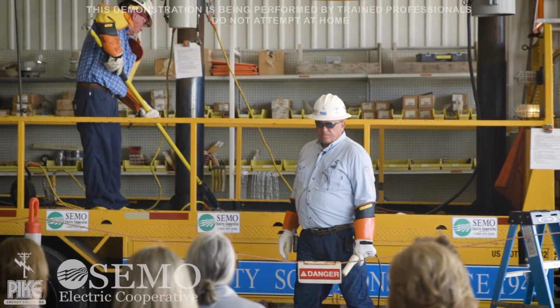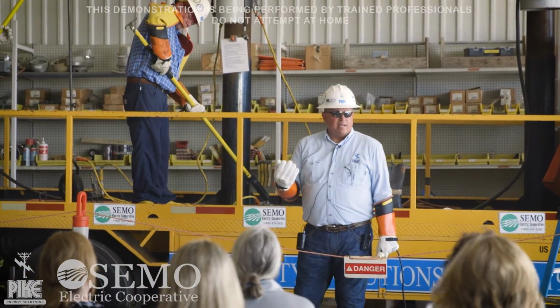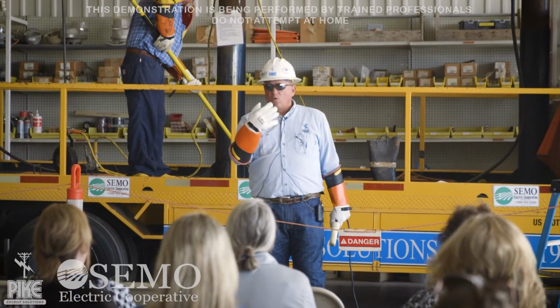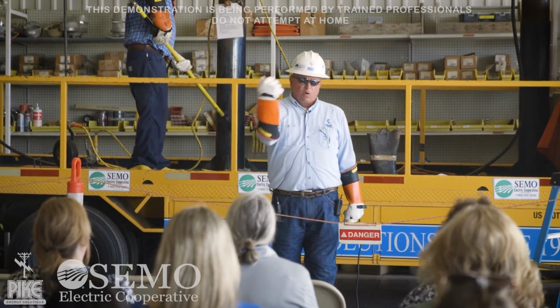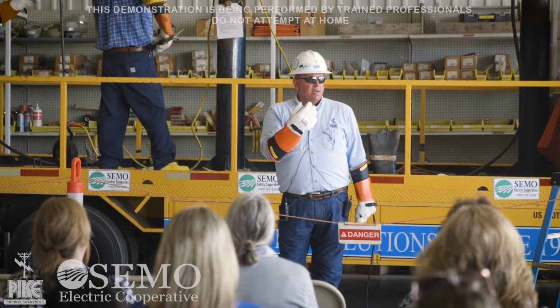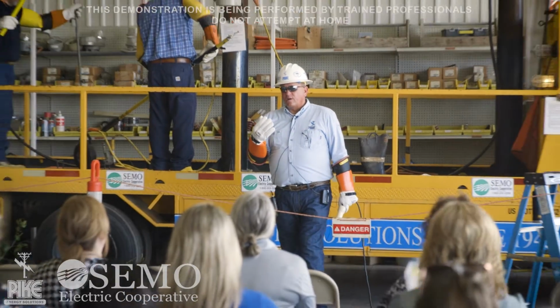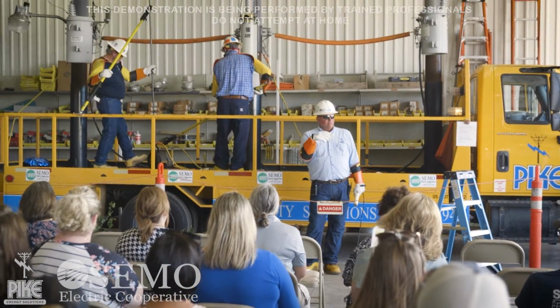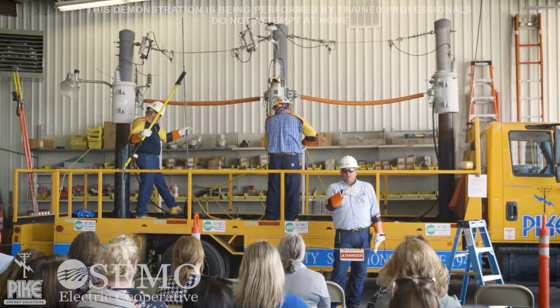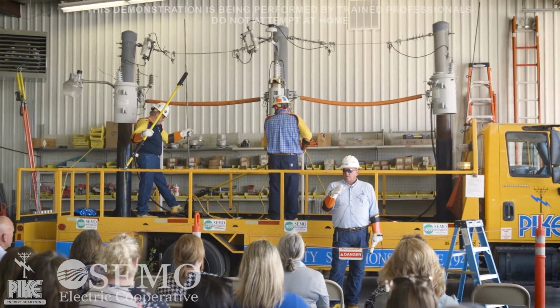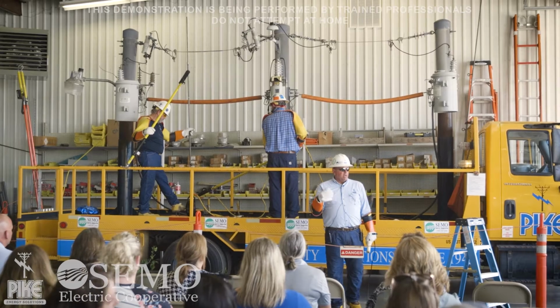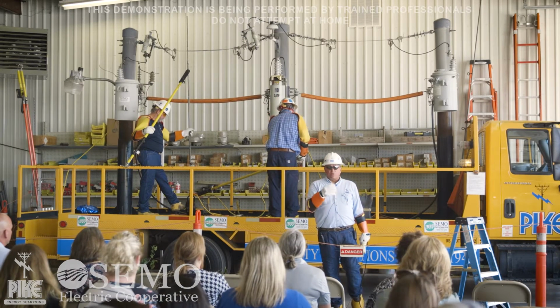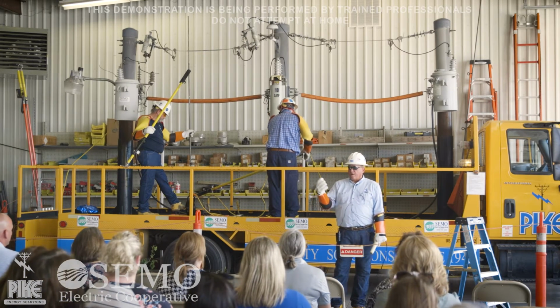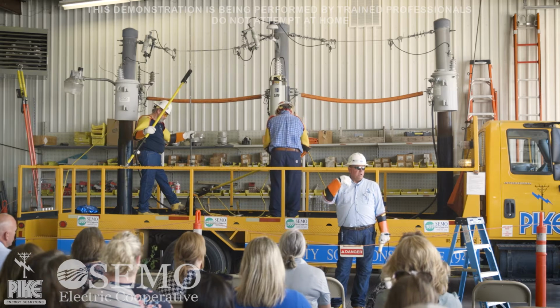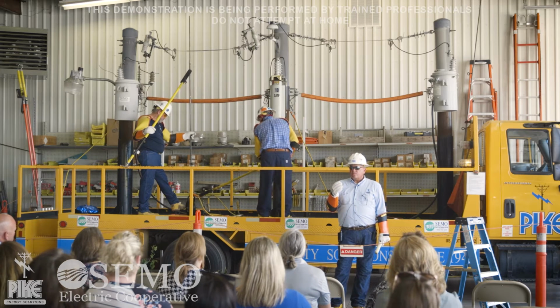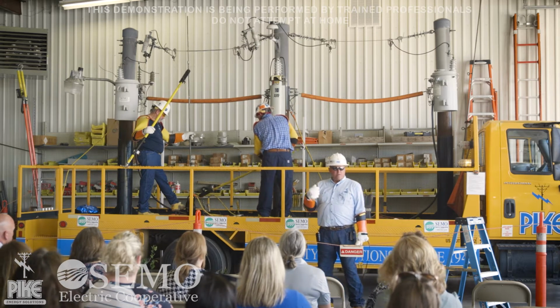But a ground doesn't work like a dam. A dam holds back that water, keeps it from going over. When we ground the line, it doesn't work that way — there's still some energy that can get past those grounds. We ground so that hopefully whatever becomes energized, those grounds cause it to trip — whether it's a breaker, a recloser, a fuse tap, or whatever, it's going to hopefully trip that or blow that fuse.